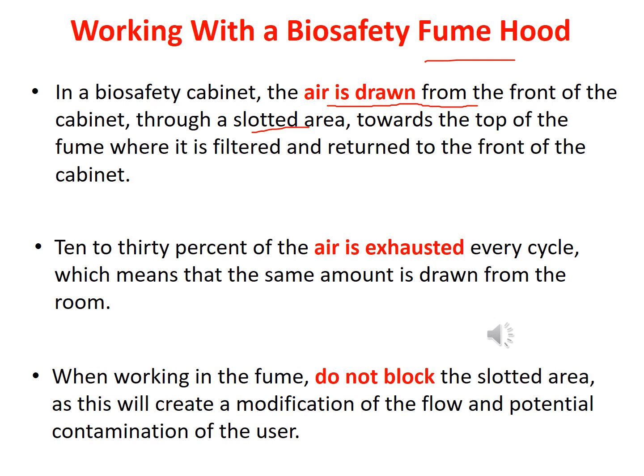This direction of air is very important, so you cannot block that particular slotted area where you are sitting. Also, 10 to 30% of air is exhausted in every cycle. So if this percentage is exhausted in every cycle, the same amount of air is definitely drawn from the room. Okay, so this is really important. Don't block that area, so that the same amount of air can be drawn.